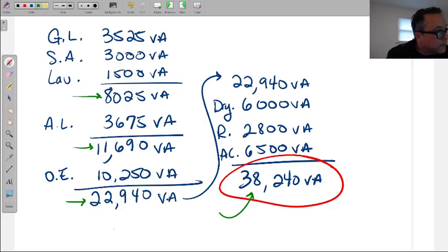Did anybody else get the 38,240? You put AL, what does the AL stand for? Those were the all other loads. Oh, okay. Yeah, the fixed in place. So that was the dishwasher plus water heater plus garbage disposal, waste disposal, and range hood multiplied by the 75%.